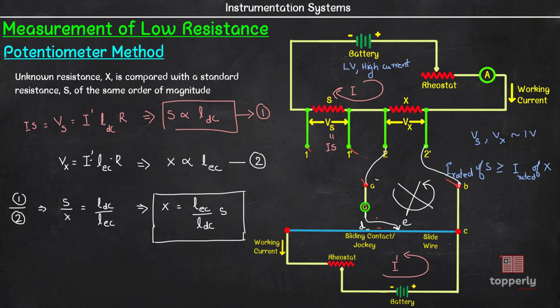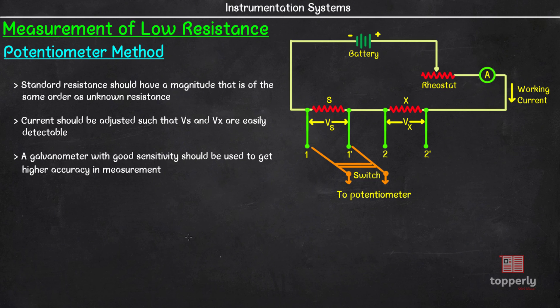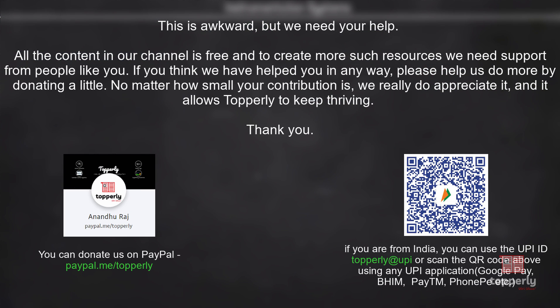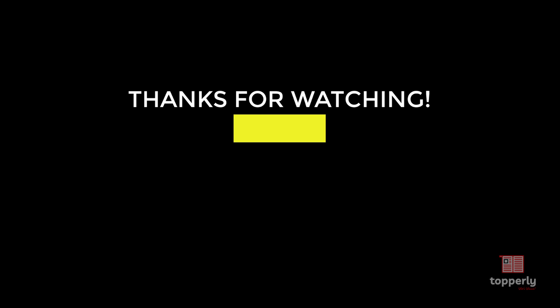The important points to remember are: first, the magnitude of the standard resistance should be of the same order as the unknown resistance. Second, the current should be adjusted such that V_s and V_x have magnitudes that are easily detectable. Finally, the accuracy of the measurement depends on the sensitivity of the galvanometer, so to get higher accuracy we need a galvanometer with good sensitivity. That's all for this lecture. Feel free to ask doubts in the comments, like the video if you found it useful, and subscribe to the channel. In the next video we will discuss the Kelvin double bridge method for measurement of low resistance.